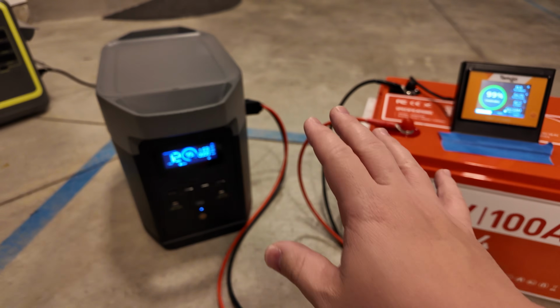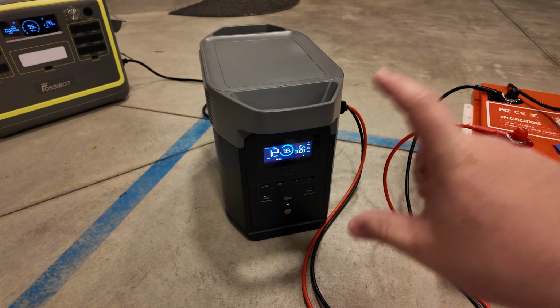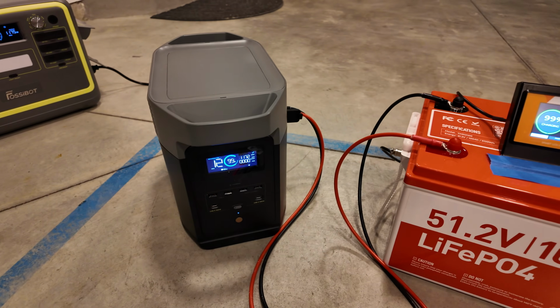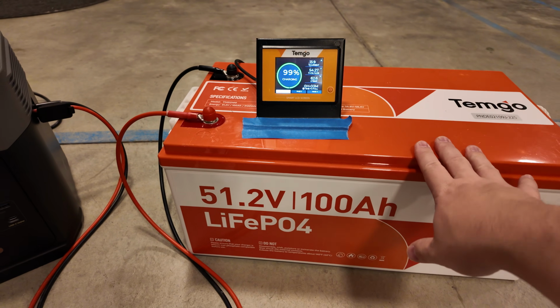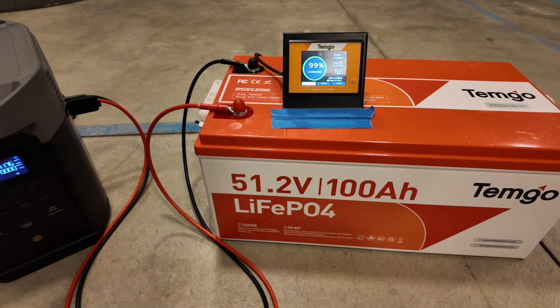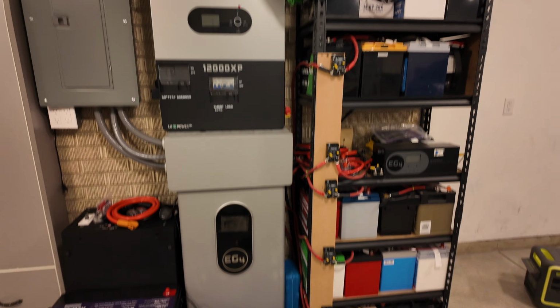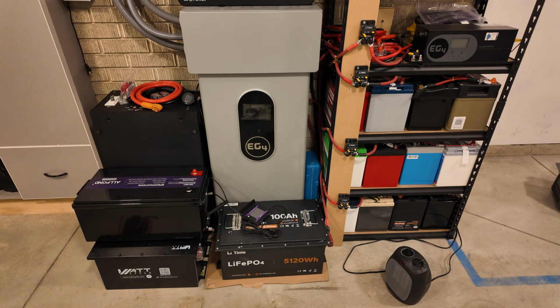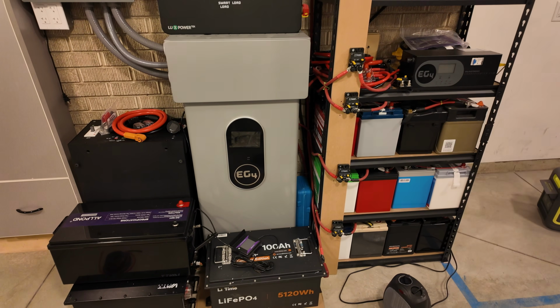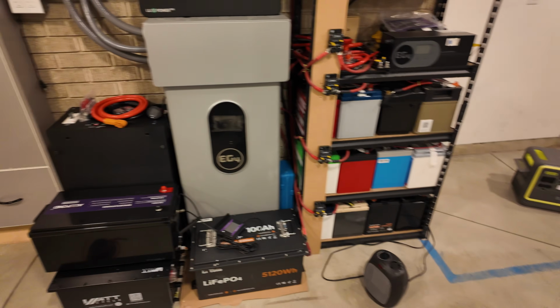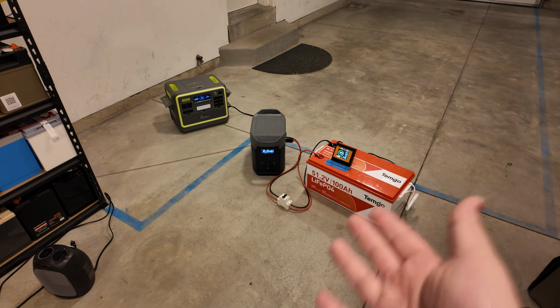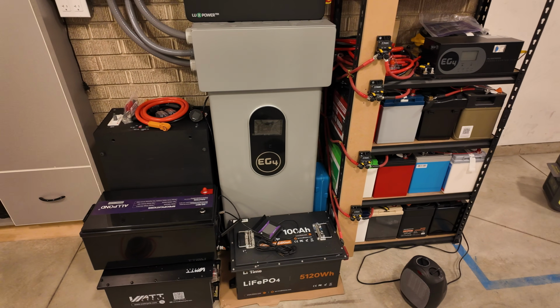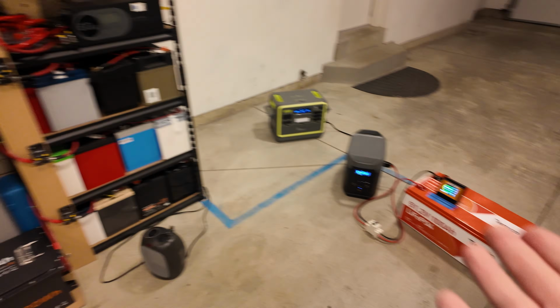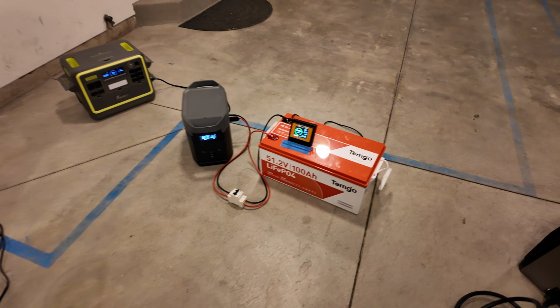So I could see a lot of you opting to go with one of these smaller units now and not even worrying about one of the bigger units, where you can get basically as much battery capacity as you want. I've got my tower of power going on over here. With proper fusing and overcurrent protection procedures taken, there's really no limit to how many batteries you could expand this on, if you engineer things correctly and size wires and overcurrent protection measures correctly.